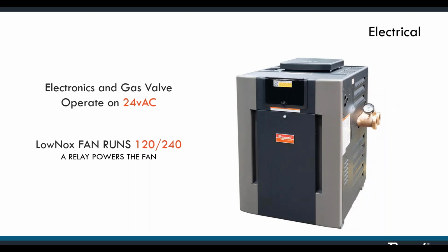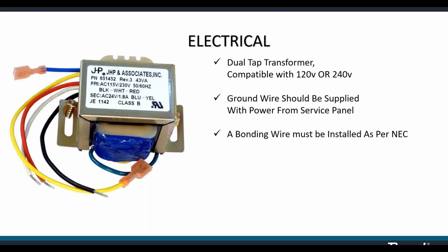On the low NOx model, the fan runs at high voltage, either 120 or 240, depending on what you have there on the property. But the electronics and the gas valve still operate on 24 volts AC. During installation, the transformer is wired to the incoming voltage, 120 or 240. After wiring, no further action is needed to accommodate voltage.